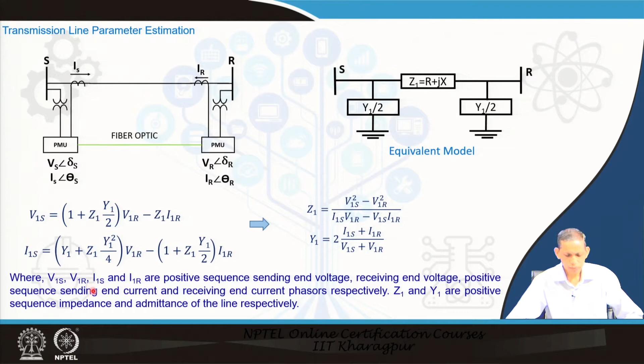So, we have this 2 bus system and the line, a 100 kilometer 400 kV 50 hertz line at a particular loading condition. PMU measurements are available as in this table, and then we have to estimate the parameters using the expressions we derived in the last slide. So, true values of this Z 1 and Y 1, the positive sequence series impedance and the shunt admittance, are given like this.